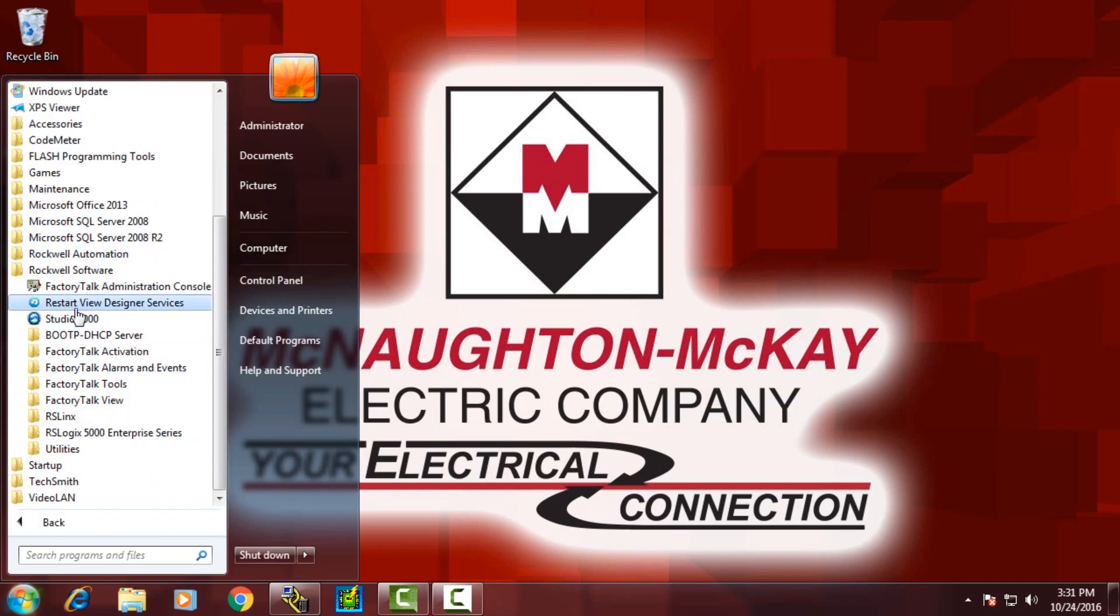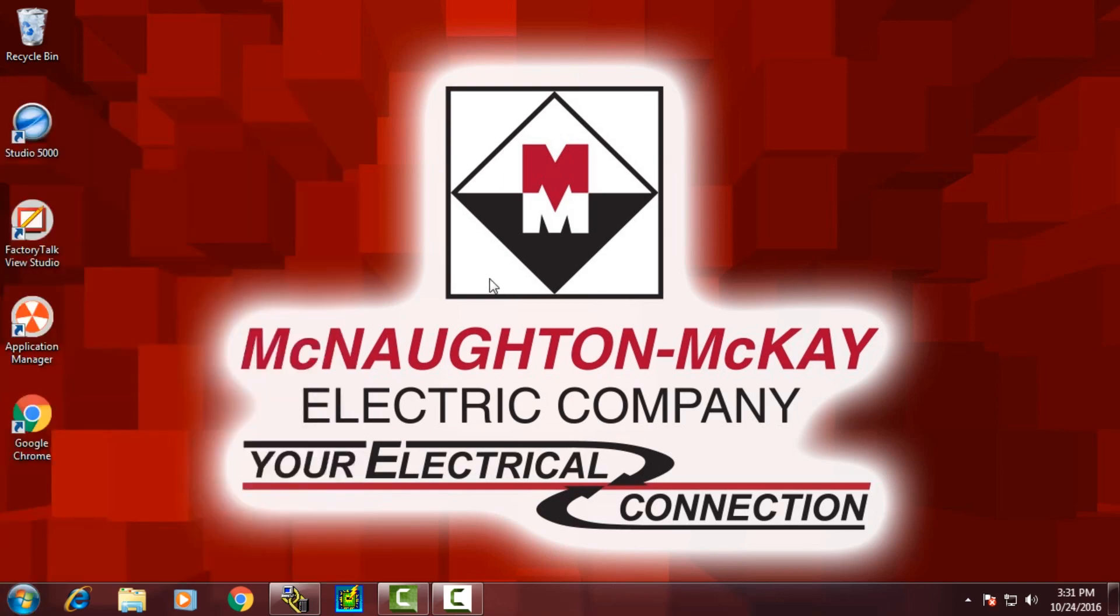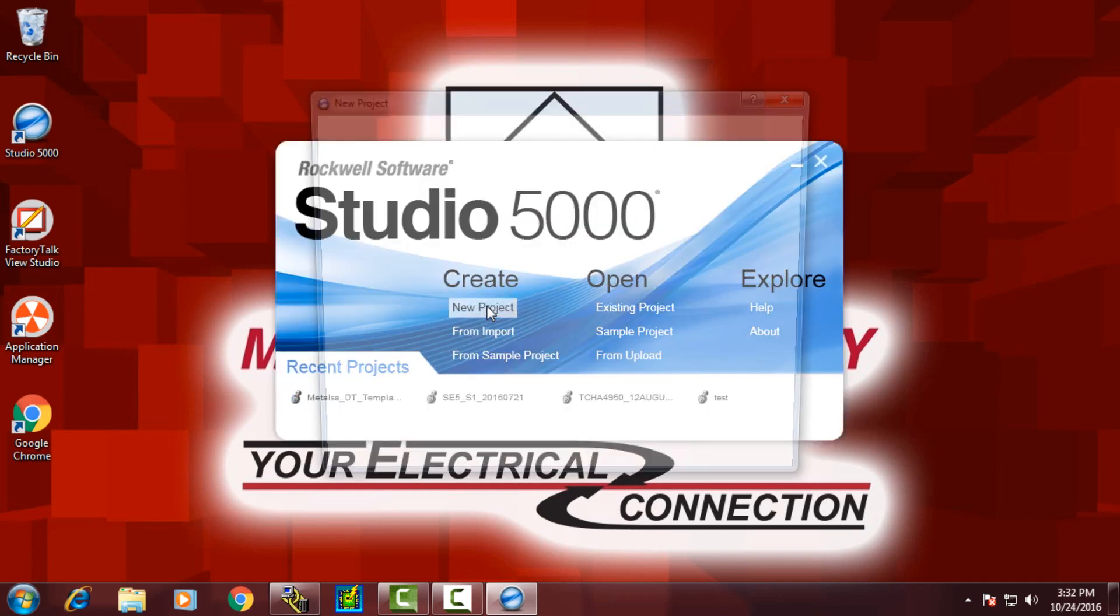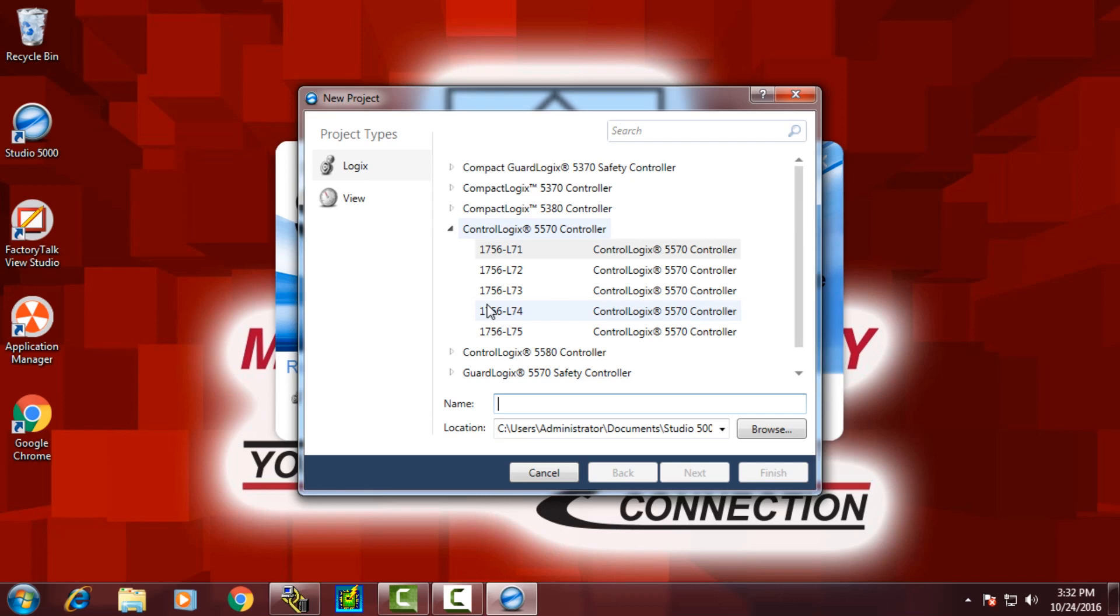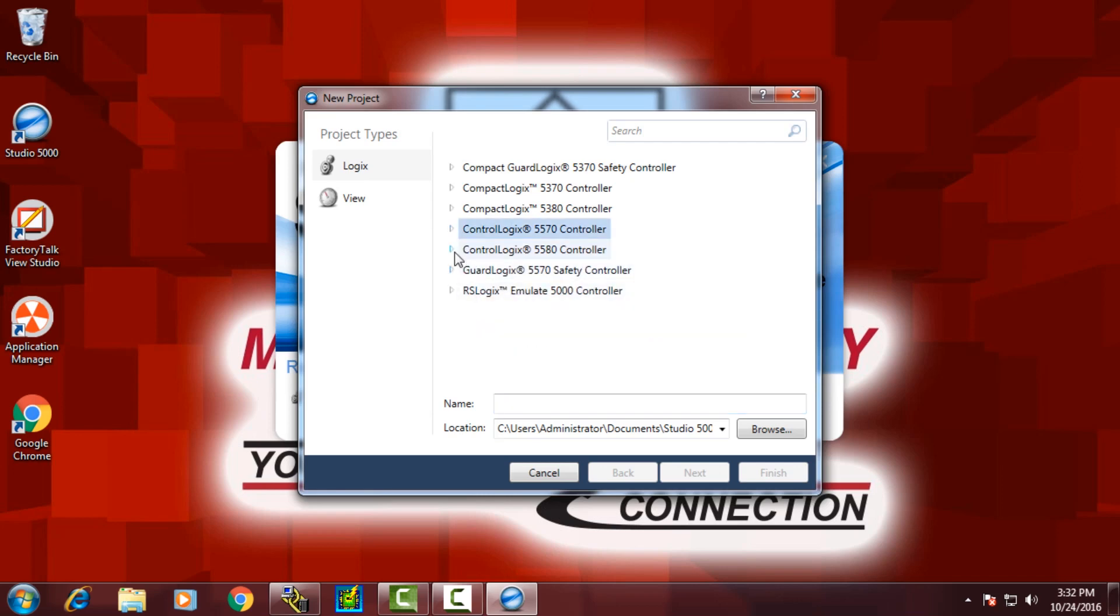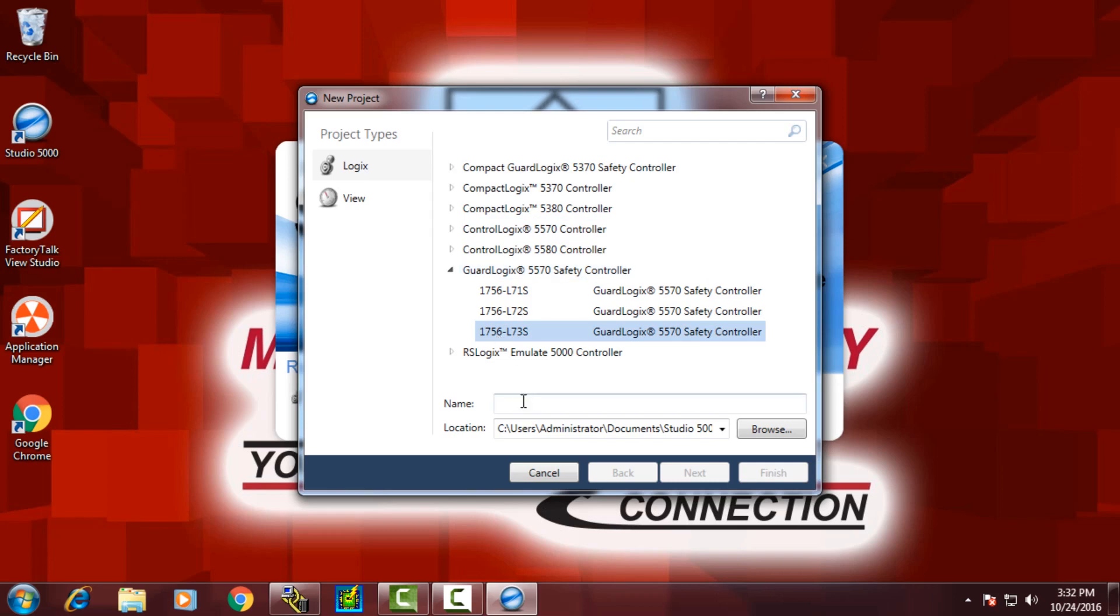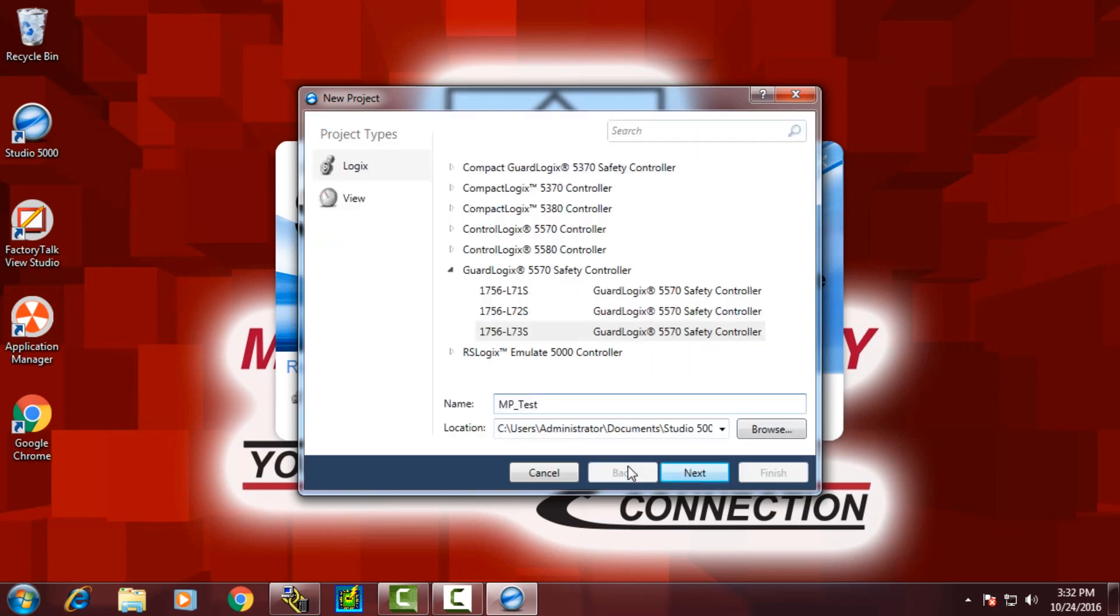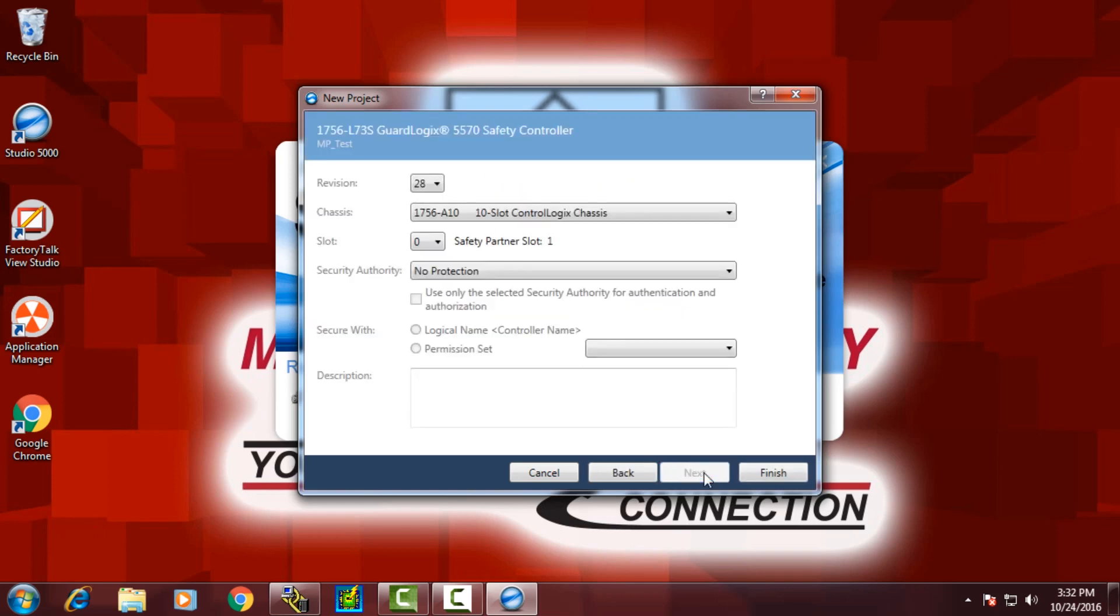To validate that the profile has properly been installed, we'll create a project in Studio 5000. Because we chose a safety I.O. block, we'll need to choose a GuardLogix controller. We pick an L73S, enter a project name, create a blank project.